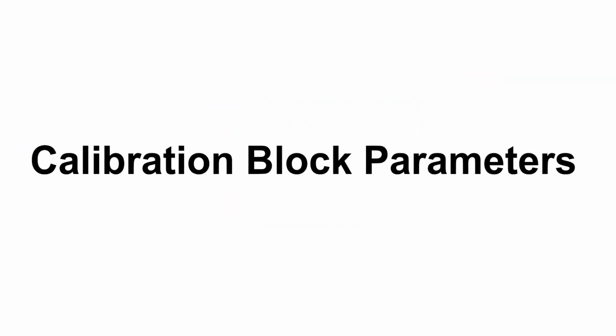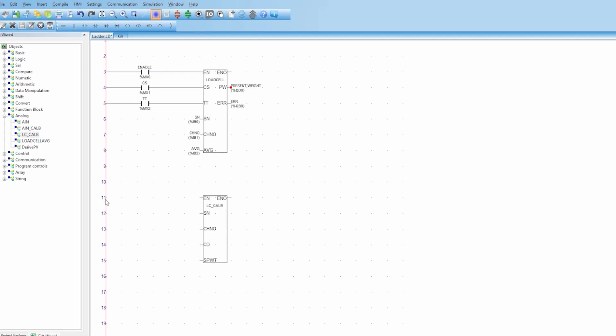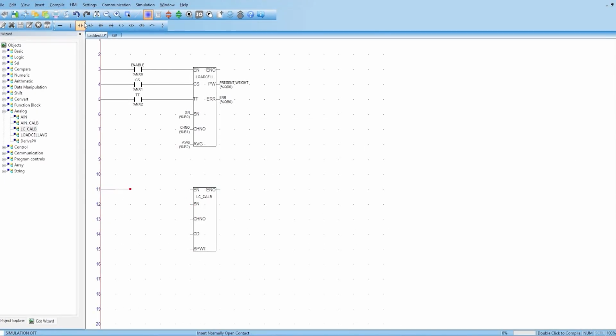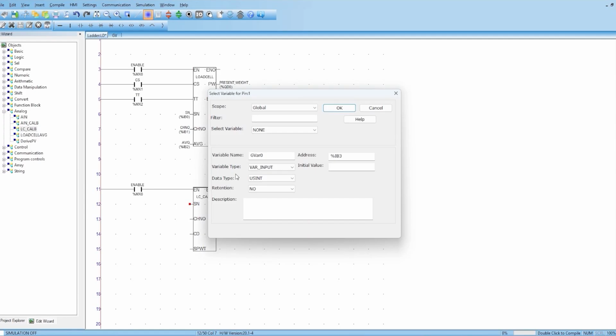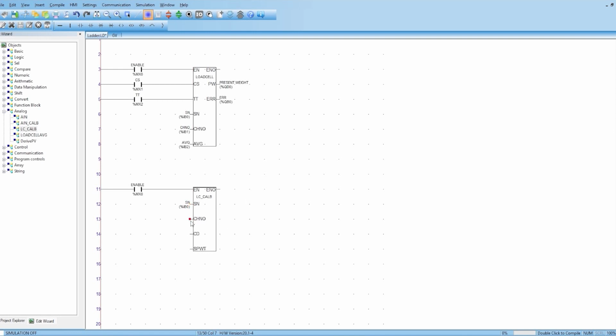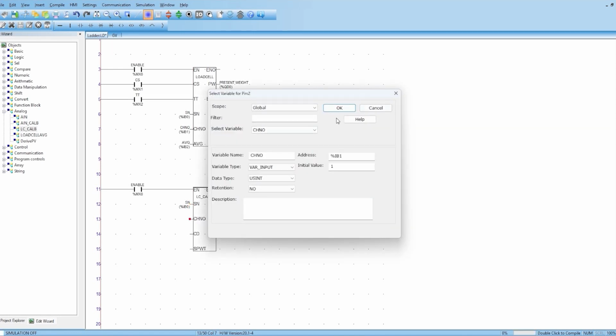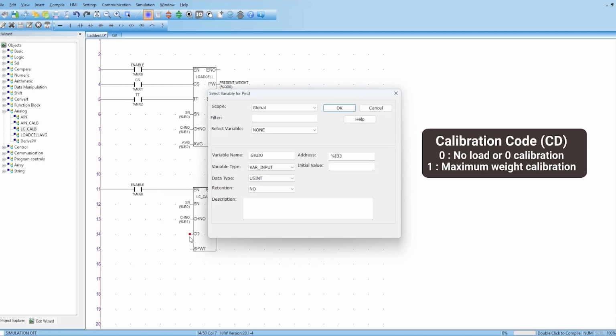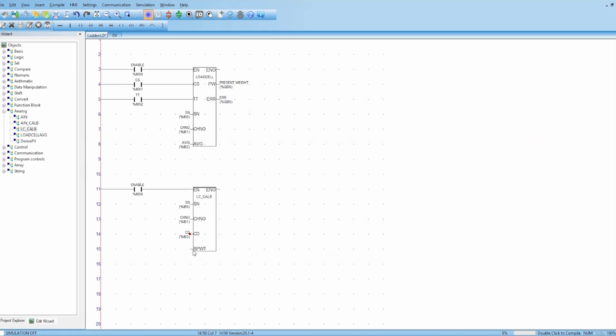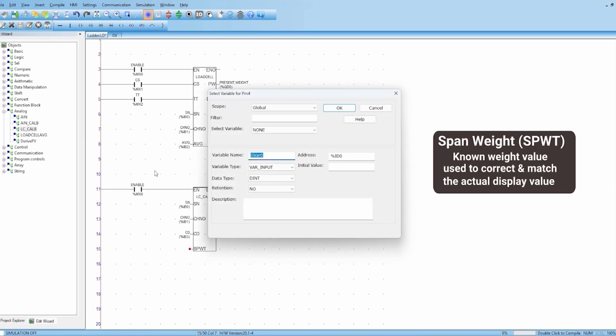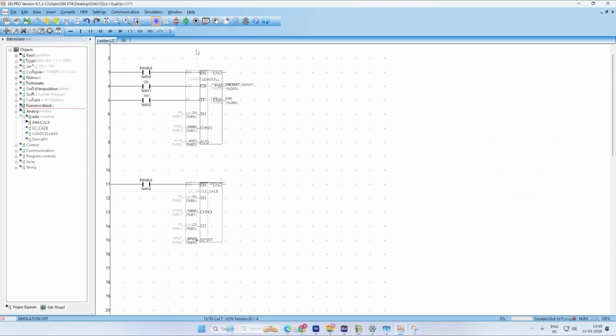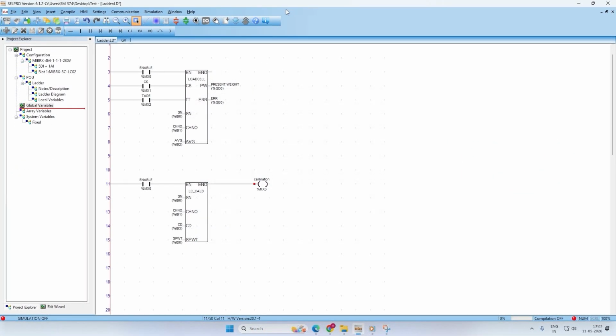Here, we are using a calibration block which consists of the following parameters. When EN is on, the load cell calibration block becomes active. SN, slot number defines the slot where the pad or module is connected. We are selecting slot number 1. Channel number, specifies which channel we want to calibrate. And we are selecting channel number 1. CD is for calibration code, 0 is for no load or 0 calibration, 1 is for maximum weight calibration. SPWT, span weight, the known weight value used to correct and match the actual display value. Connect calibration coil to ENO.